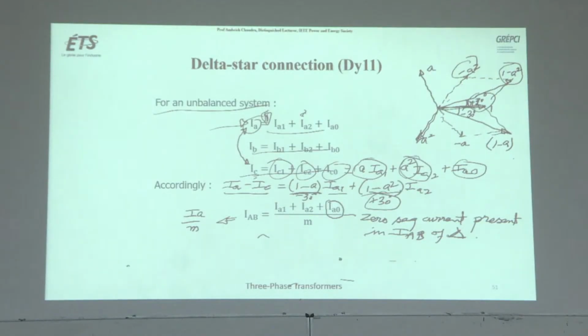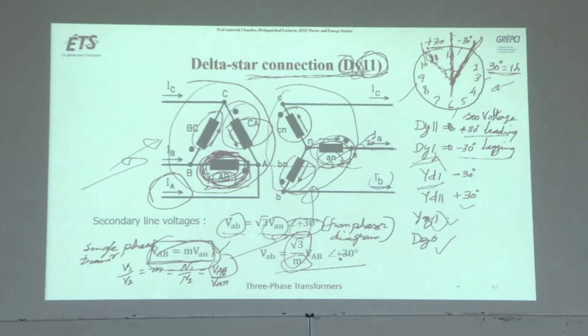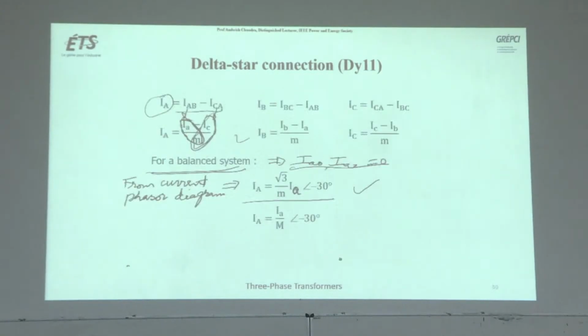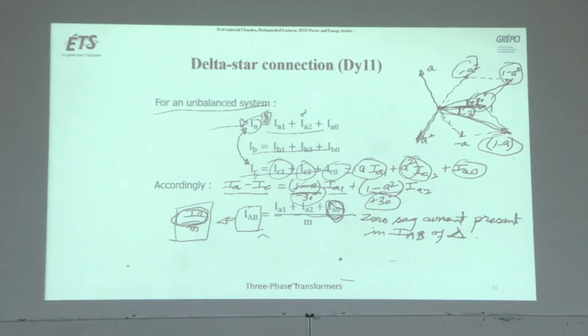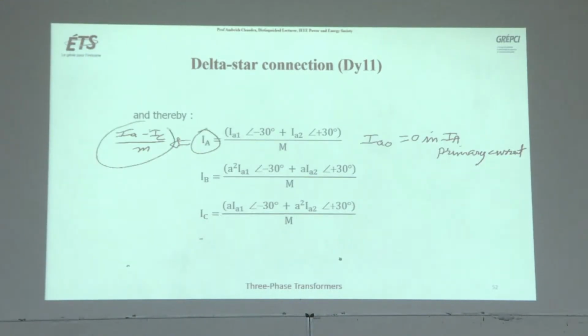And 1 minus A, this will give you 1 minus A, this is minus 30 degree phase shift. Okay, so what you can see, IAB is the current, this is the equation we have seen in single phase transformer, and IA, if it is distorted, it has IA1, I2, IA0. So zero sequence current is present. So if we say IAB, here you see zero sequence currents are present, IA0, IB0, IC0. But if you calculate IA using this equation, okay, zero sequence currents are absent here.